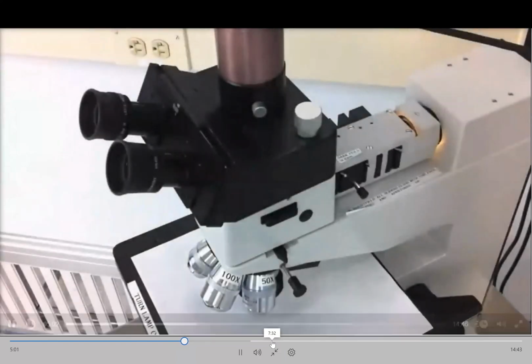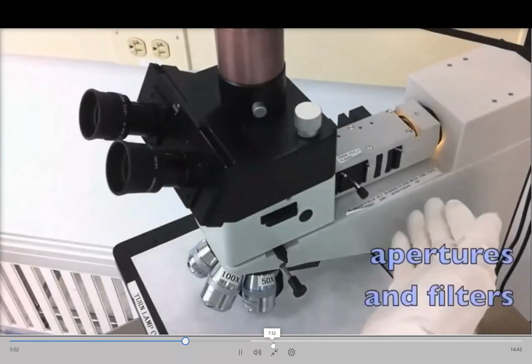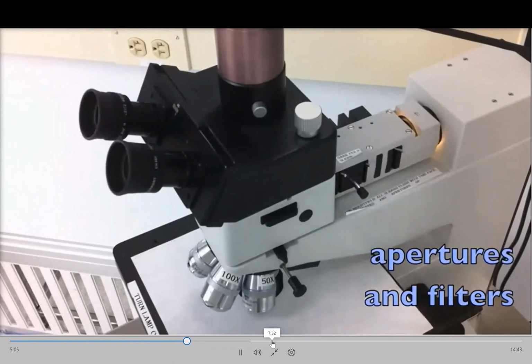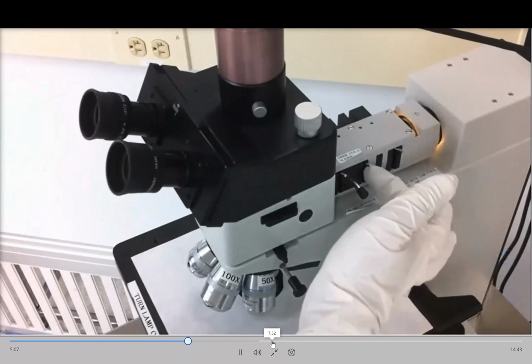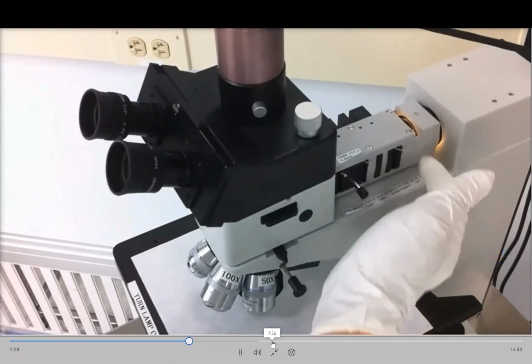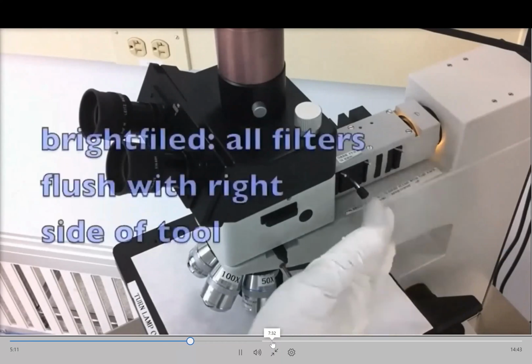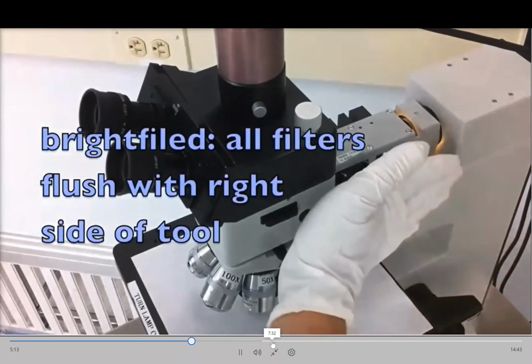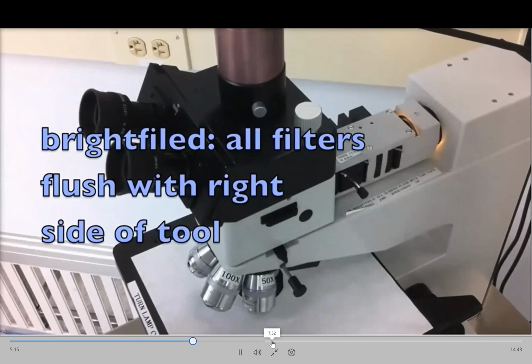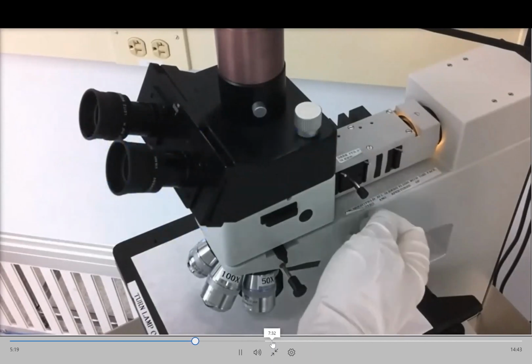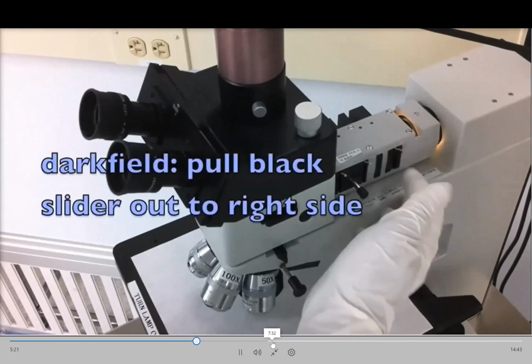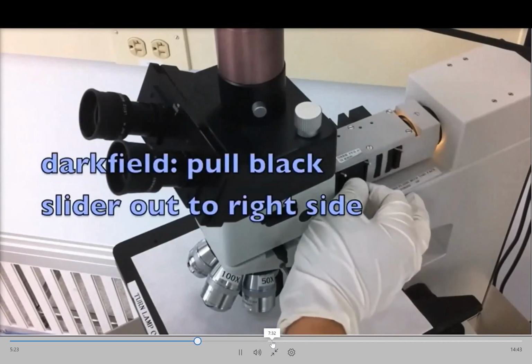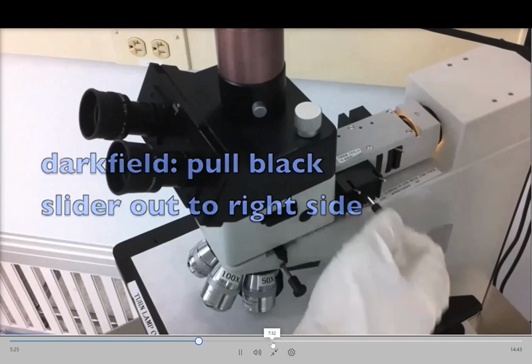From a top view of the tool, we can see that there are various apertures and filters. All the small gray levers should be in the up position as shown. And for bright field imaging, all the adjustable black filters should be pushed in so that they are flush with the right side of the tool, as shown here. For dark field imaging, keep the silver levers up, but pull this black sliding box out towards the right side of the tool.